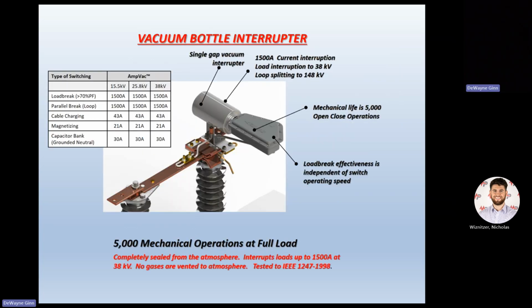So if we want to go to a higher ampacity, and we like to do this at 38 kV and above, this particular one is a good one for 38 kV. This is called a V4. It's a vacuum bottle in here instead of a probe inside of it. In vacuum, there's no arcing and sparking, so there won't be any smoke coming out. And there's no way for smoke to come out because it's all enclosed in a vacuum bottle. So what you see is a vacuum bottle on the backside, the round part, and the front part is the mechanical operator that operates the bottle.